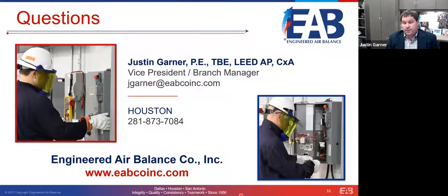We're seeing a lot more, especially on the ECM side of things. And I didn't cover that today because it's a whole different conversation to have. But we're seeing manufacturers that are using, especially direct drive ECM motors, and the motor nameplate says one thing, but the way that the manufacturer applies that motor is very different. And so in those particular cases, you have to use the nameplate that's on the outside of the equipment, which is usually an air handling unit, fan coil unit, something like that. And that's, you know, an engineered system. So you're going to use the nameplate on the outside of the equipment. I hope that helps.